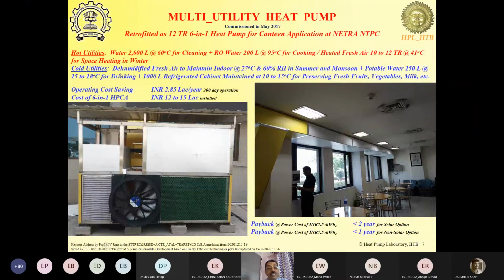The first utility is cooling and dehumidification of fresh air to maintain the indoors at 27 degrees and 60% RH. Note that the temperatures are selected in such a way that they do not increase the cooling and dehumidification utility significantly. And yet it is comfortable enough.